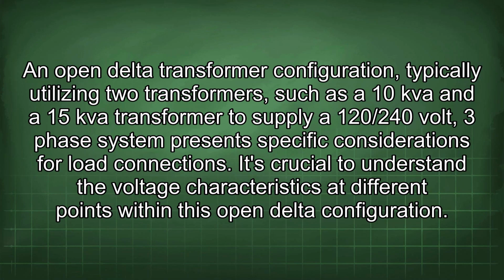An open delta transformer configuration, typically utilizing two transformers, such as a 10 kVA and a 15 kVA transformer to supply a 120/240 volt three-phase system, presents specific considerations for load connections. It's crucial to understand the voltage characteristics at different points within this open delta configuration.